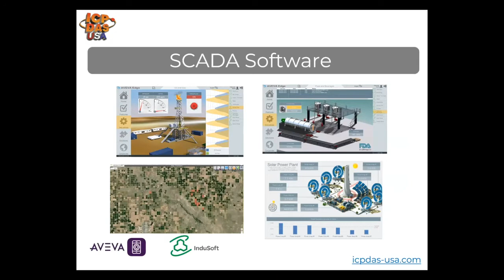Our ET7000 series modules communicate over Modbus TCP and are configurable over a web page. They can be used with standard Ethernet switches, routers, and hubs, and can be networked with standard Ethernet cabling. They support operating temperatures from -25°C to 75°C, which can be extended with conformal coating for $25. They come in a wide range of configurations of analog inputs, analog outputs, digital inputs, and digital outputs. They support I/O pairing, so the inputs on one can be configured to trigger the outputs on another.